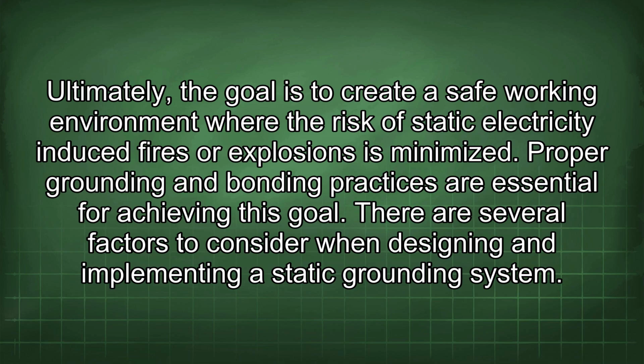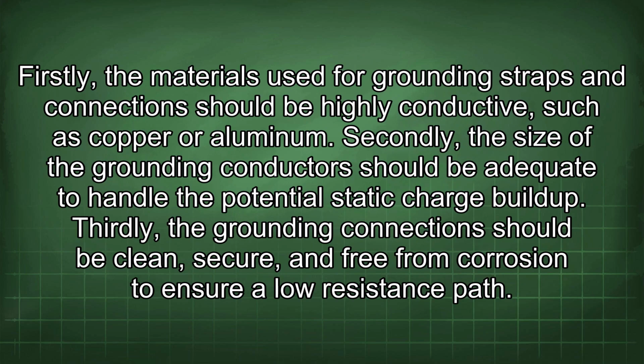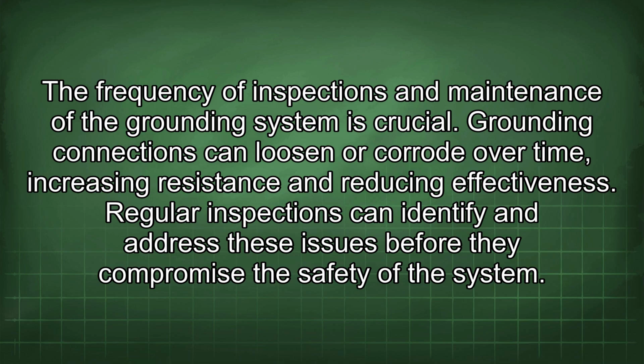There are several factors to consider when designing and implementing a static grounding system. Firstly, the materials used for grounding straps and connections should be highly conductive, such as copper or aluminum. Secondly, the size of the grounding conductors should be adequate to handle the potential static charge buildup. Thirdly, the grounding connections should be clean, secure, and free from corrosion to ensure a low resistance path. The frequency of inspections and maintenance of the grounding system is crucial. Grounding connections can loosen or corrode over time, increasing resistance and reducing effectiveness. Regular inspections can identify and address these issues before they compromise the safety of the system.